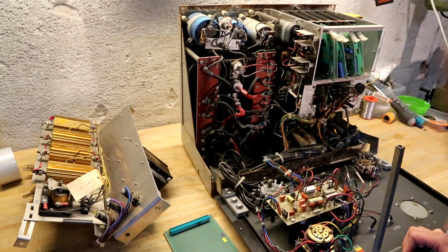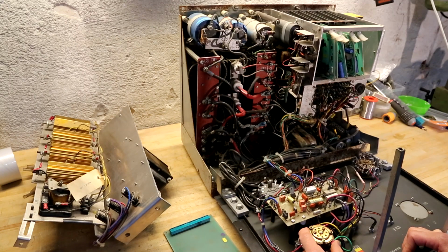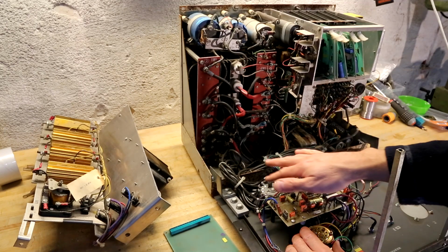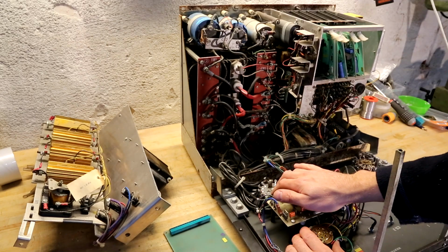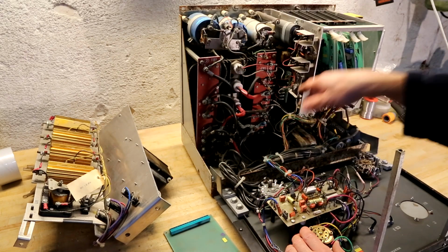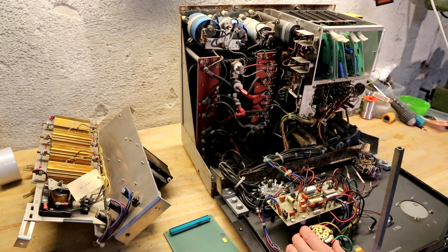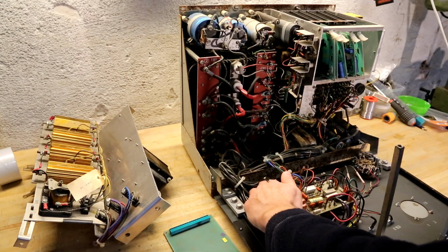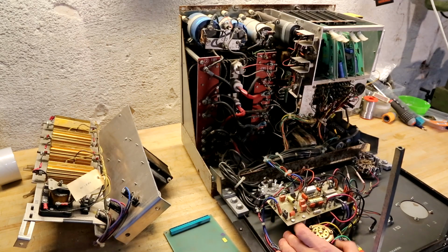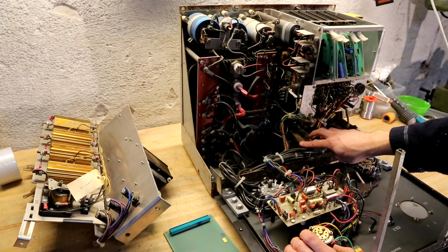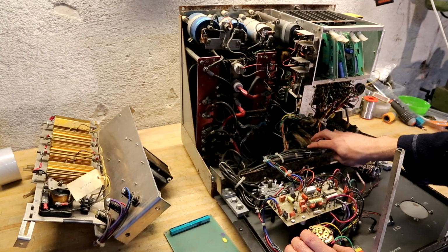You actually had to dump the pulses of this DC voltage from the bank, from a square wave, into a step up or step down transformer. So the selection you make on this kilovolt peak switch actually goes through a step up transformer, which then goes to the primary of the high voltage transformer. So that's how you select between 50 and 110 kilovolt peak. Then the inverter just short circuits the battery bank into that step up transformer. Along with that, we have the probably filament transformer sitting down here.